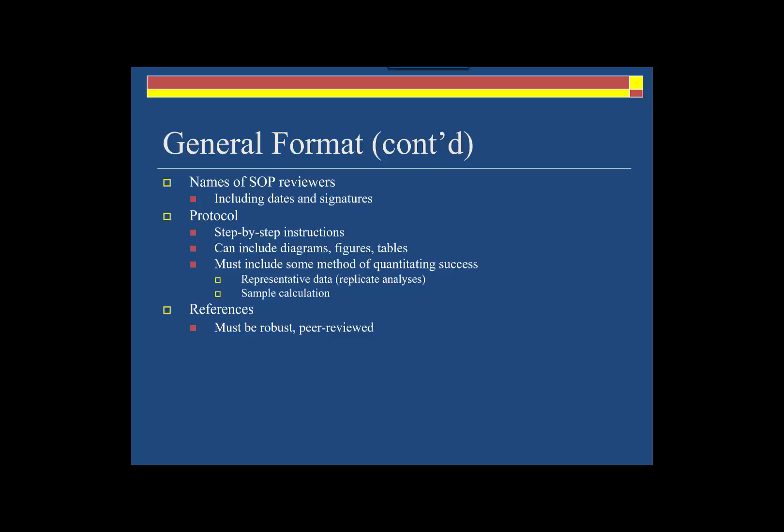SOPs should be reviewed and revised regularly. When they're reviewed, the date of the revision and the revision number should be specified. The next section is the heart of the document, and that's the protocol itself. The protocol should detail everything from turning on the instrument and preparing the samples through to analysis and interpretation of any data obtained. Figures and tables are extremely helpful, and so are sample calculations. More is better when writing an SOP.